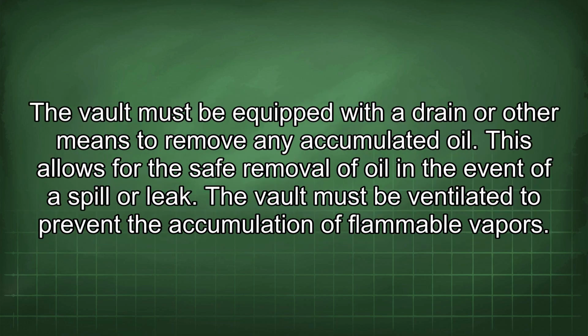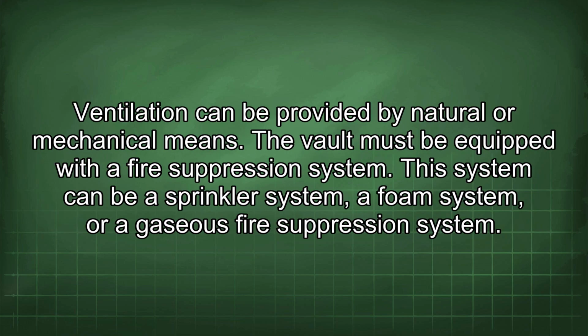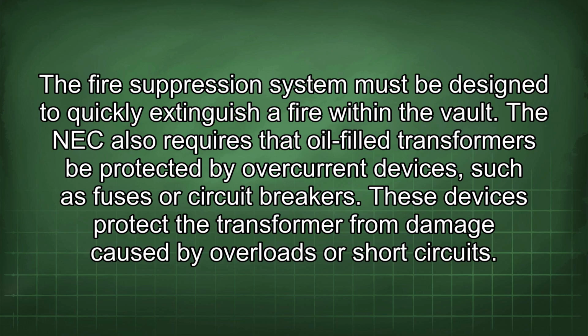The vault must be equipped with a drain or other means to remove any accumulated oil. This allows for the safe removal of oil in the event of a spill or leak. The vault must be ventilated to prevent the accumulation of flammable vapors. Ventilation can be provided by natural or mechanical means. The vault must be equipped with a fire suppression system. This system can be a sprinkler system, a foam system, or a gaseous fire suppression system. The fire suppression system must be designed to quickly extinguish a fire within the vault.